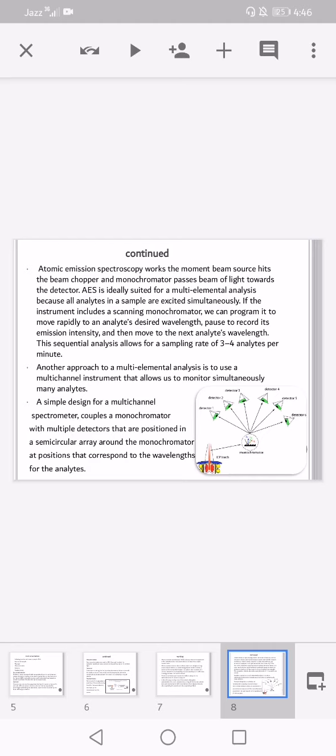This sequential analysis allows for a sampling rate of three to four analytes per minute. Another approach to multi-elemental analysis is to use a multi-channel instrument that allows simultaneous monitoring of many analytes. A simple design for a multi-channel spectrometer couples a monochromator with multiple detectors positioned in a semicircular array around the monochromator at positions that correspond to the wavelengths for the analytes, as illustrated here.